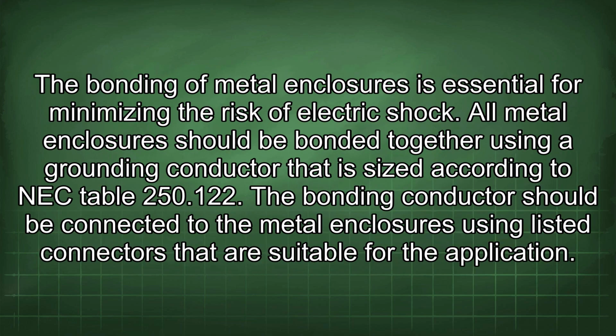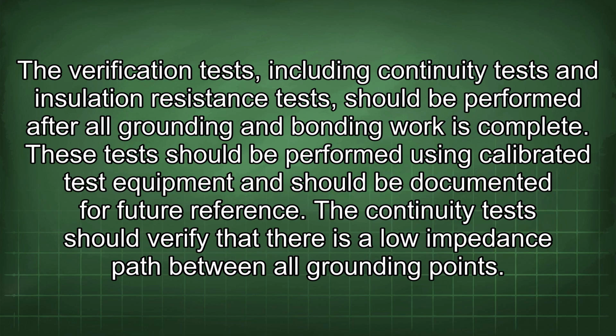The bonding of metal enclosures is essential for minimizing the risk of electric shock. All metal enclosures should be bonded using a grounding conductor that is sized according to NEC Table 250.122. The bonding conductor should be connected to the metal enclosures using listed connectors that are suitable for the application. The verification tests, including continuity tests and insulation resistance tests, should be performed after all grounding and bonding work is complete. These tests should be performed using calibrated test equipment and should be documented for future reference.